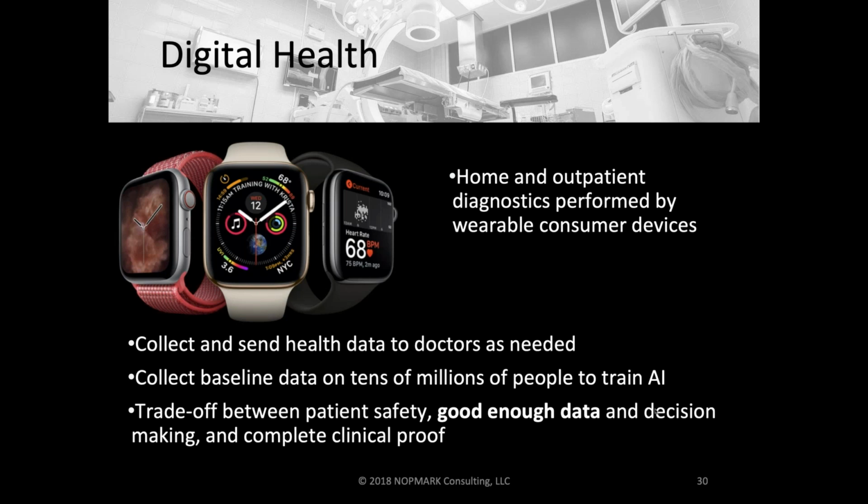So how this was tested was very different than other medical devices. A lot of it was tested on a lot of healthy people. For the watch, they ran clinical studies for the last probably a year or so. They collected a lot of data from healthy individuals using the watch who subscribed to the app on the watch, and it was testing based on that data, both clinical testing, the algorithm testing, and the software testing.